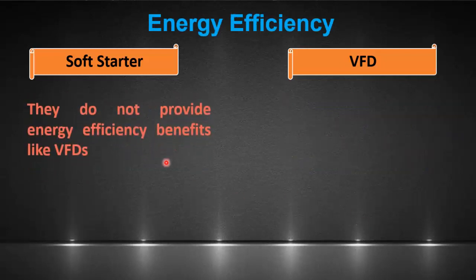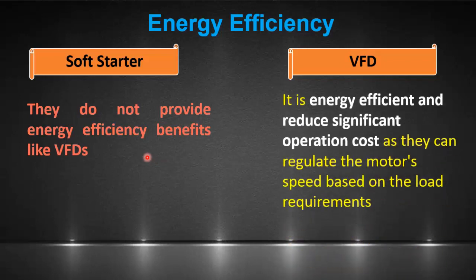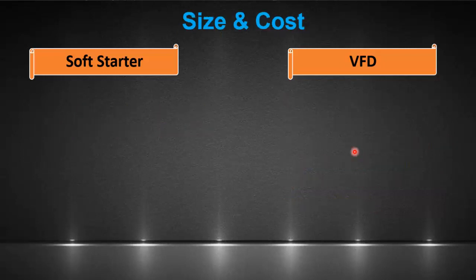Soft starters do not provide energy efficiency benefits like VFDs. Once the motor reaches full speed, it operates at the same efficiency as without a soft starter. VFDs are known for their energy-saving capabilities as they can regulate the motor's speed based on load requirements. By running the motor at lower speeds when full speed is not necessary, VFDs can significantly reduce energy consumption and costs.